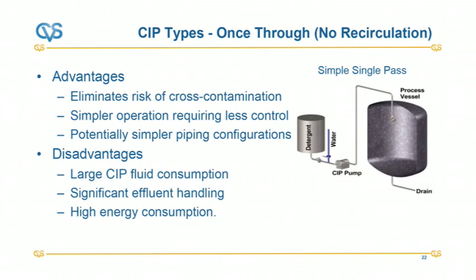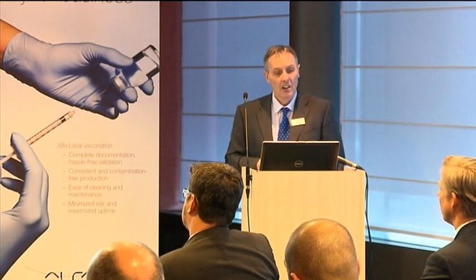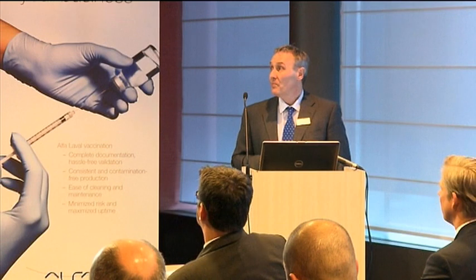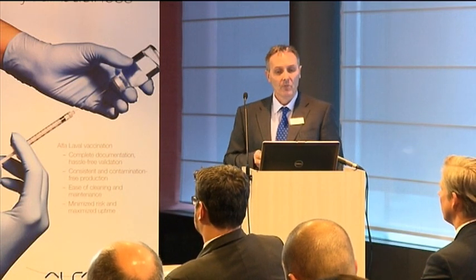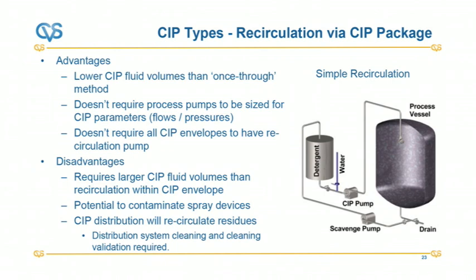Now, the advantages are it eliminates the risk of cross-contamination from the CIP system. It is simpler, and it requires less control. Potentially simpler piping configurations as well. The disadvantages are quite large. A large CIP fluid consumption, especially if we've got static spray balls, which tend to use more volume. Significant effluent handling, high energy consumption. So quite often I've seen that, but it isn't a very effective way of cleaning in terms of the cost.